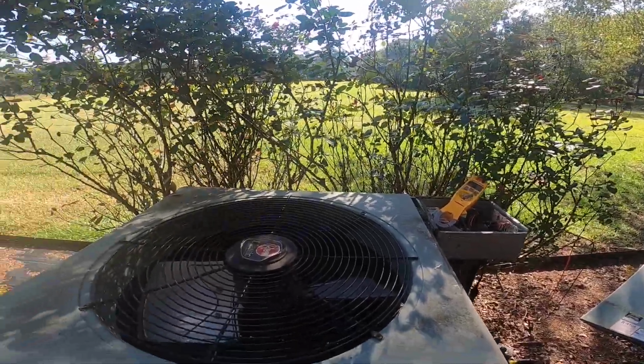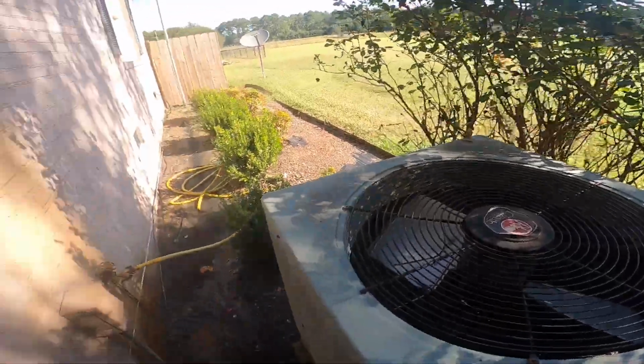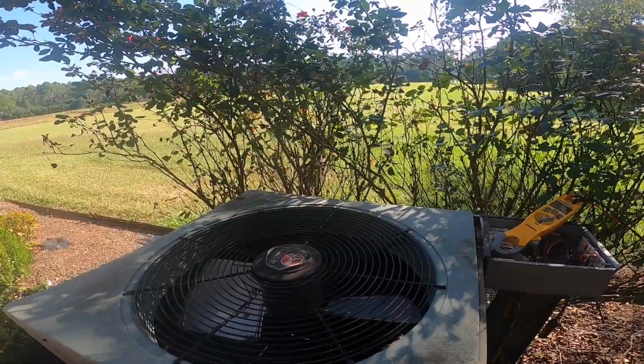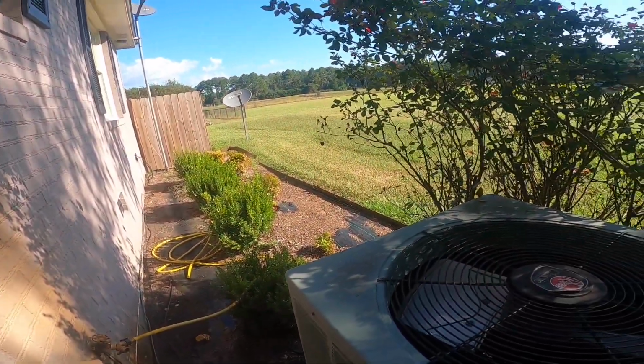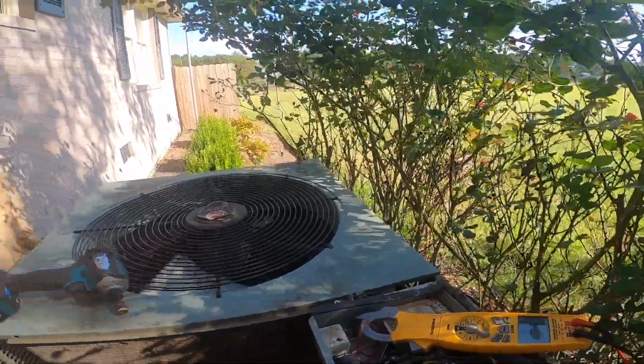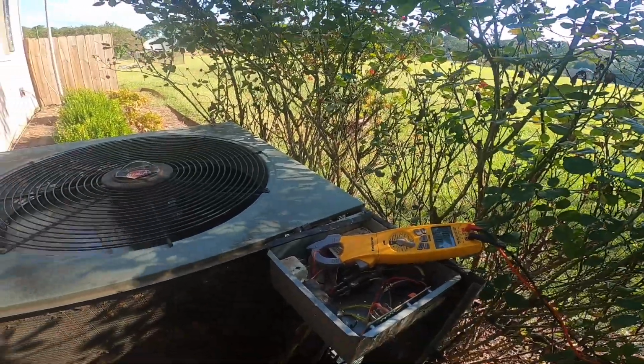Now on this call, if I had just addressed a complaint, which was a thermostat that would intermittently go blank, we wouldn't have found the clogged drain, holes in the return in the attic, nor this fan. So that's just a reminder that you gotta check both ends if it's a split. So I'm gonna give them a quote on a new fan motor and bill them for what we've done, and see if they want to change it.